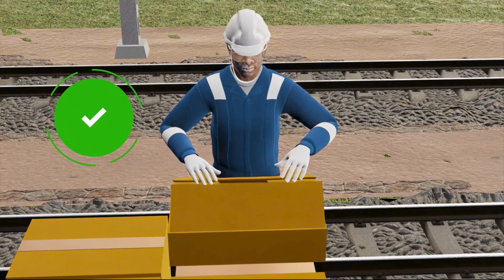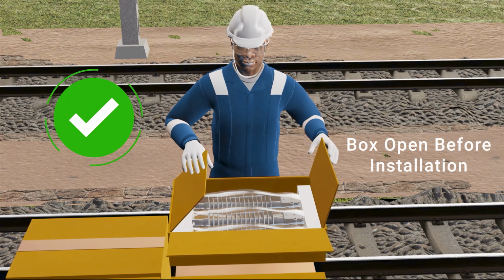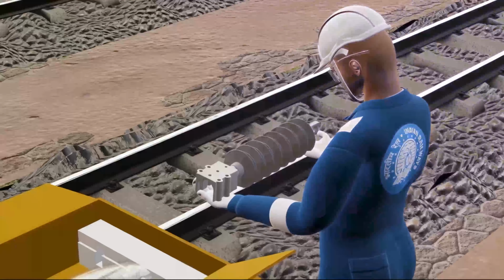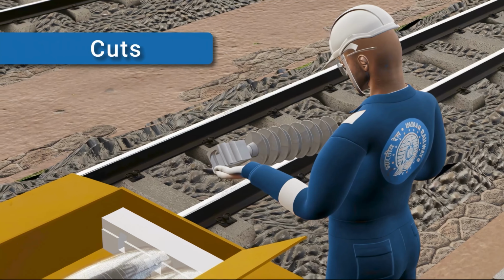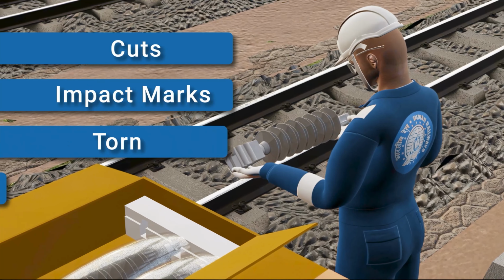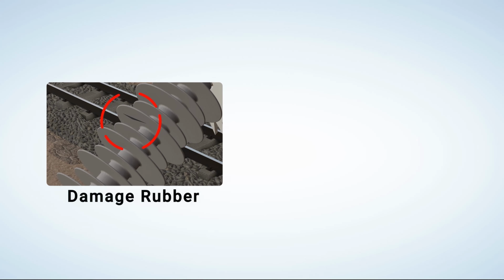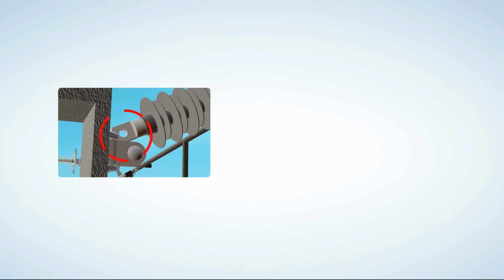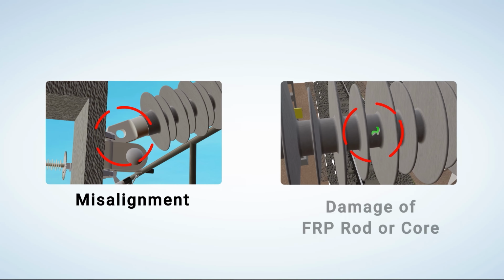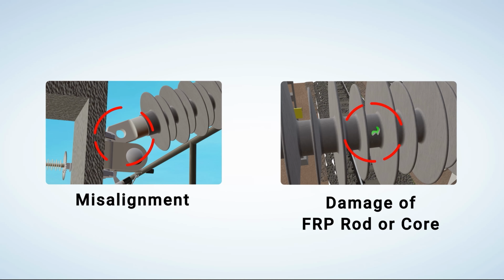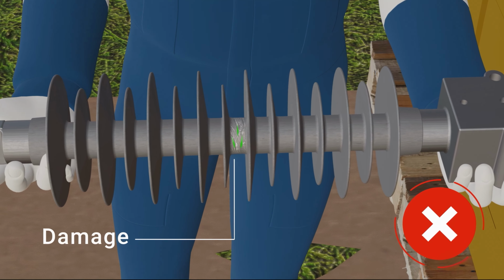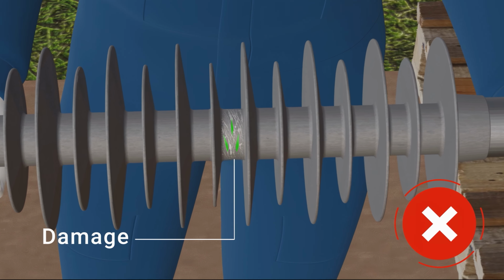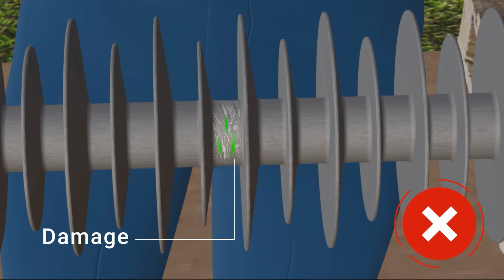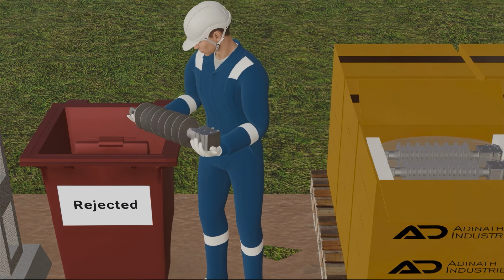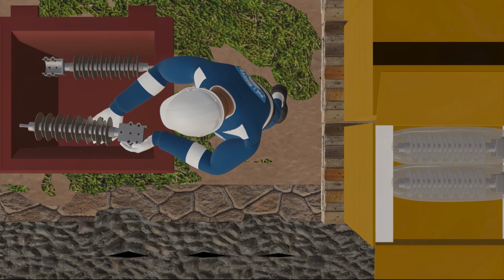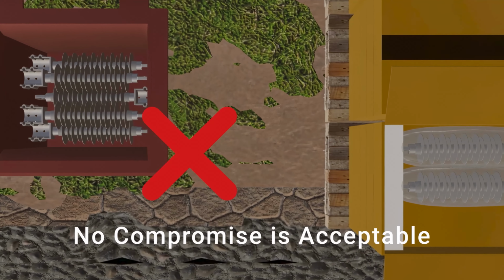At the worksite, the carton box should be opened only just before installation. Each insulator must be thoroughly inspected for cuts, impact marks, torn or broken sheds, damage to the rubber housing, damaged end seals, misalignment of metal fittings, or any exposure of the FRP rod or core. If even the slightest exposure of the FRP rod or damage to the core is detected, the insulator must be segregated/rejected immediately. No compromise is acceptable.